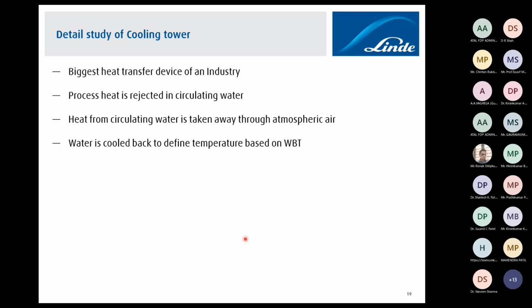So water is cooled back to a definite temperature based on the wet bulb temperature condition, because we cannot operate the way we wish. It depends on the wet bulb temperature. During evaporation, because the majority of the heat transfer takes place due to evaporation, some amount of water also gets carried away into the atmosphere due to wind or, as somebody said, in a mechanical cooling tower, it has a fan. That fan also carries away some of the air plus water droplets.